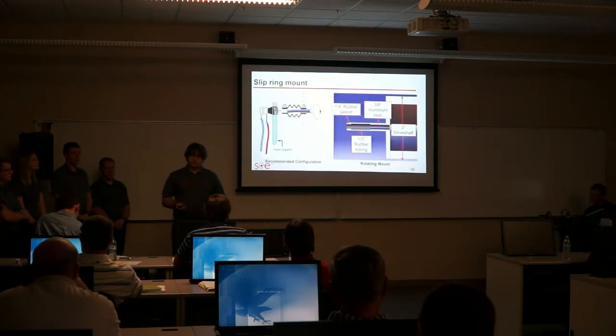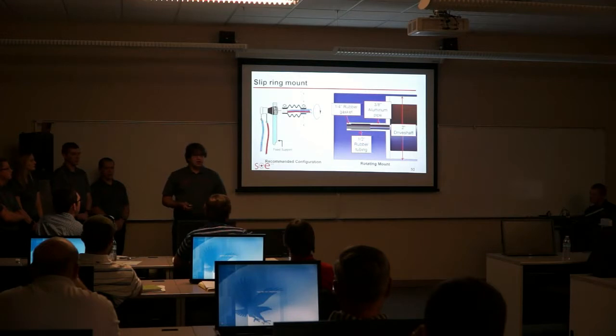In order to use a slip ring, we need to mount it. The recommended mounting configuration is shown in the picture on the left. This was provided by Mercotac. What this shows is that the main body of the slip ring is held by a rigid mount, and the rotating side of the slip ring is held by a vibration dampening mount.